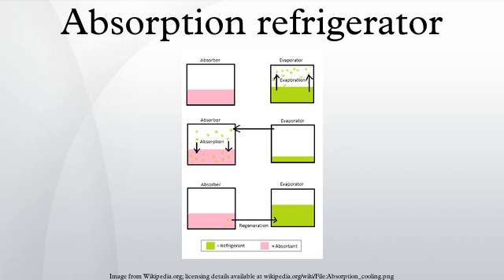Another difference between the two types is the refrigerant used. Compressor refrigerators typically use an HCFC or HFC, while absorption refrigerators typically use ammonia or water. A simple absorption refrigeration system common in large commercial plants uses a solution of lithium bromide salt and water. Water under low pressure is evaporated from the coils that are being chilled. The water is absorbed by a lithium bromide water solution. The water is driven off the lithium bromide solution using heat.